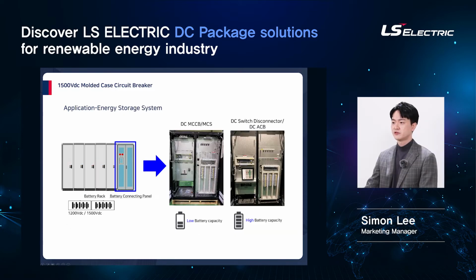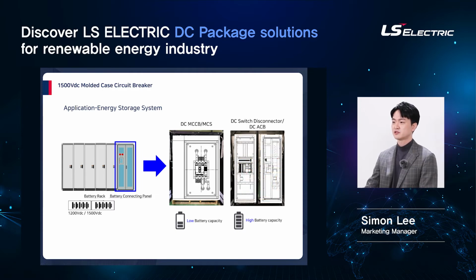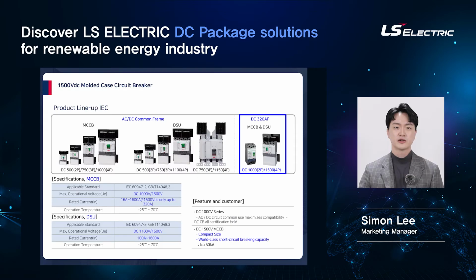Another example is energy storage system. In this system, normally battery cell or modules are protected by BPU and BCP. In BCP application of a smaller capacity, DC MCS or MCCB cells are commonly used with fuse. Here I would like to show you IEC DC MCCB and MCS types. Especially our 250 amps, 1500 DC volts breaker with compact size would be appropriate solution for PV power plant with the capacity below 500 kilowatts.